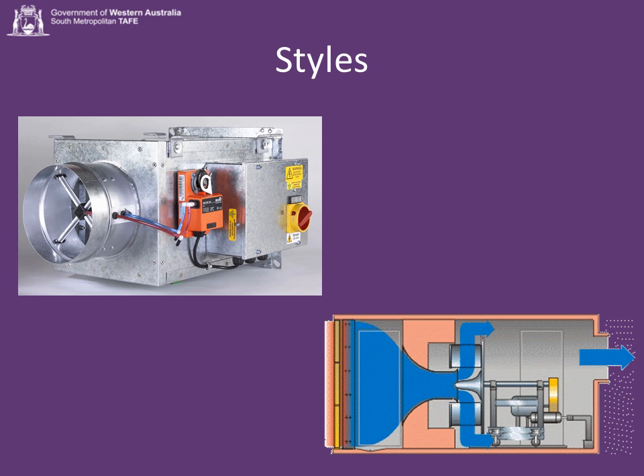At the front left there, you can see the airflow sensor, the pipes with the small holes in them. Two pressure sensing pipes, a red and a blue, are coming off from that, and they're going into the orange thing, which is a Belimo controller. That's got a little motor on it, you see, and the shaft coming through so that it can move the shaft left and right, or clockwise and anti-clockwise. Next to that, the other silver box with the isolator on it, that's the controller for the electric duct heater.